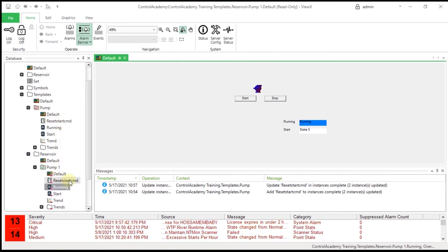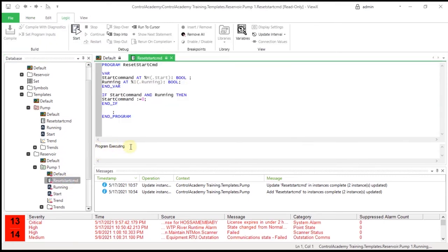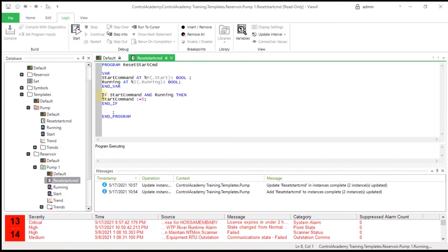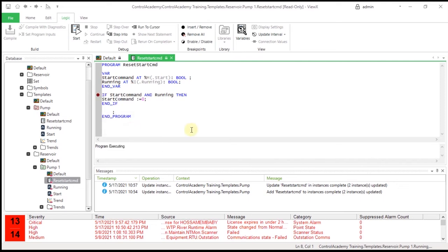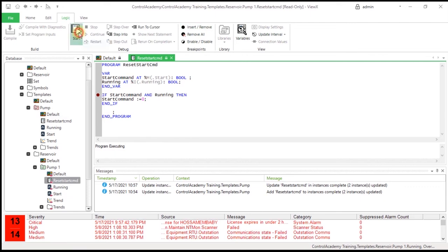Open the logic program in the Pump1 instance. The statement 'program executing' should be displayed in the messages window. Click the program line 'IF start command AND running THEN' and press the F12 key to insert a breakpoint on this line, or right-click and select Insert Breakpoint from the menu. This means that each time ClearSCADA tries to execute this line of the program, it stops and waits for you to tell it what to do. A breakpoint shows as a red dot in the left margin of the code. Select the Logic tab and click Start on the ribbon. You should see the red dot highlighted by a yellow arrow, indicating that the code execution has arrived at the breakpoint and is waiting for user intervention.